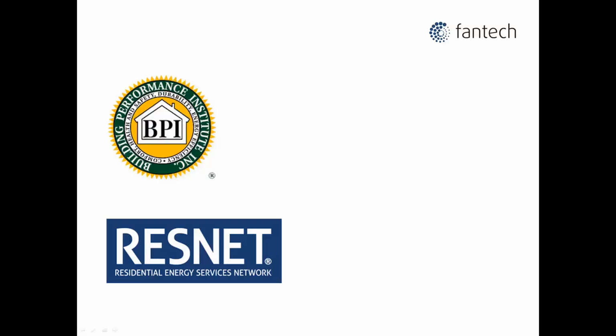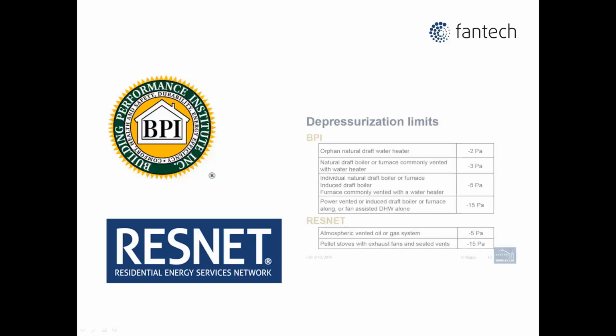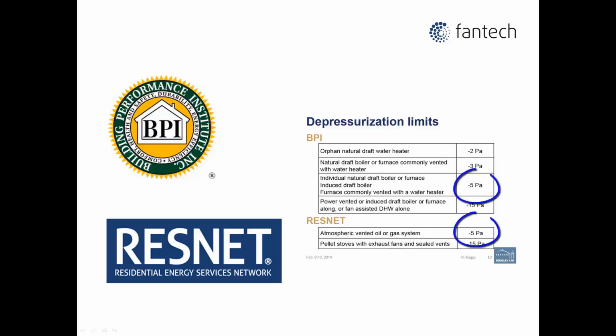The Building Performance Institute and Residential Energy Services Network develop standards for depressurization limits in residential appliances. As you can see, it doesn't take much to cause depressurizations in today's tight homes. -5 pascals for an atmospheric vented water heater equates to 0.02 inches of water column.